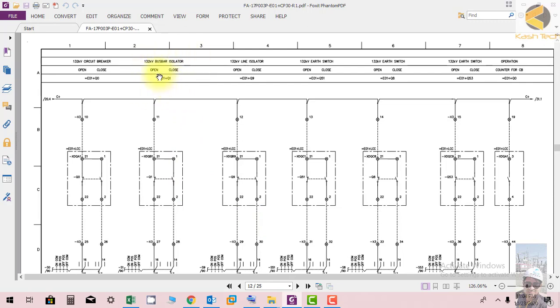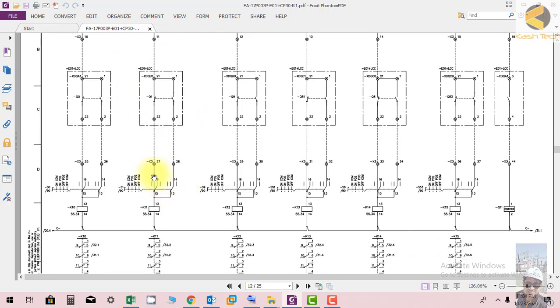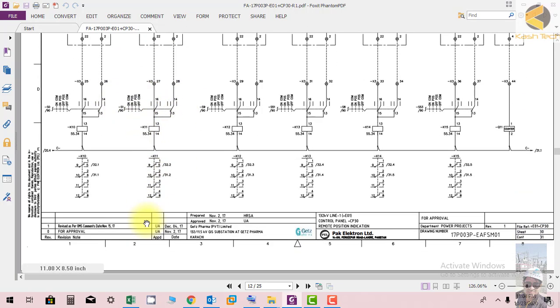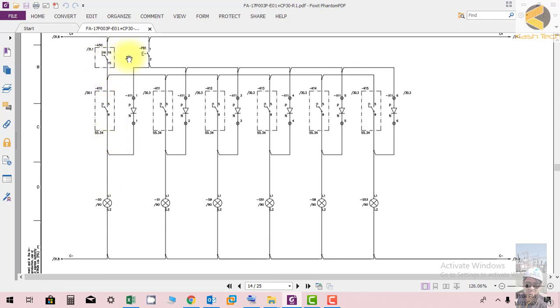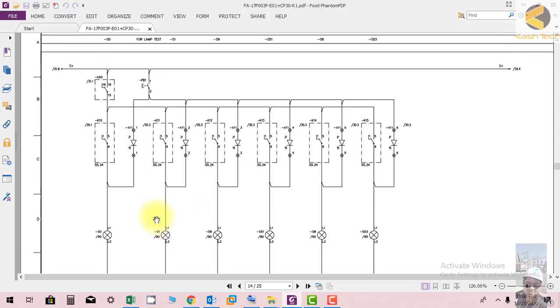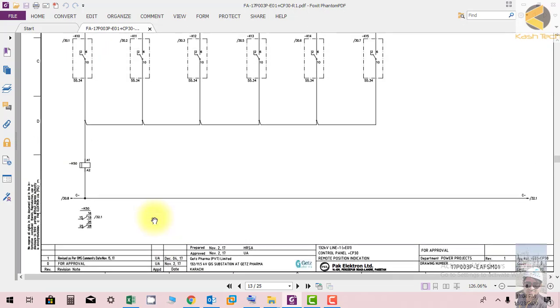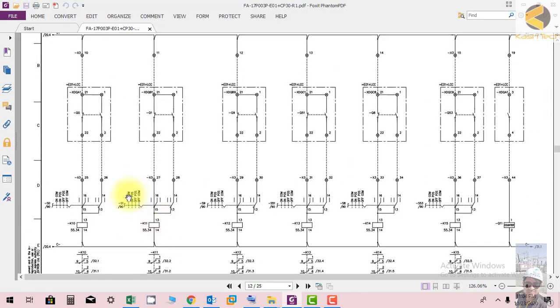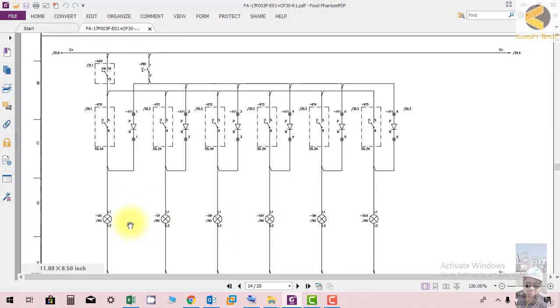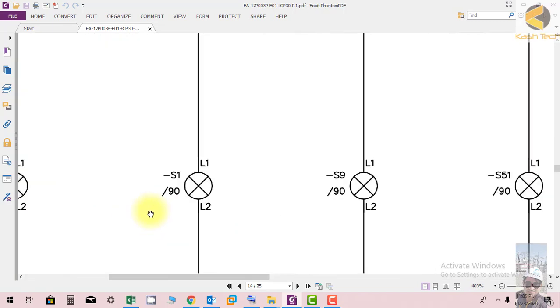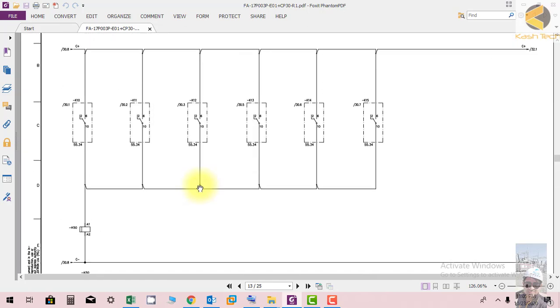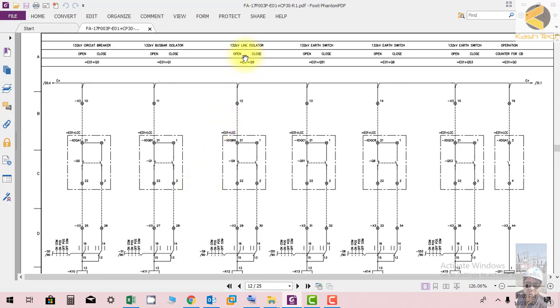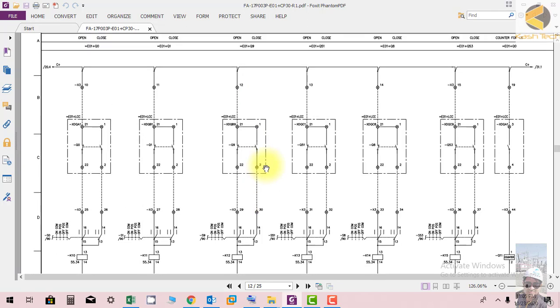In the same way, other lights will also work. If there is a discrepancy between the bus bar isolator status in the yard and the discrepancy switch on the control panel, K11 will pick up. When K11 picks up it will energize the flicker relay, and the flicker relay will provide flickering supply. K11 picked up will also energize S1, providing light to the discrepancy switch S1. This S1 light is installed inside the control switch S1.